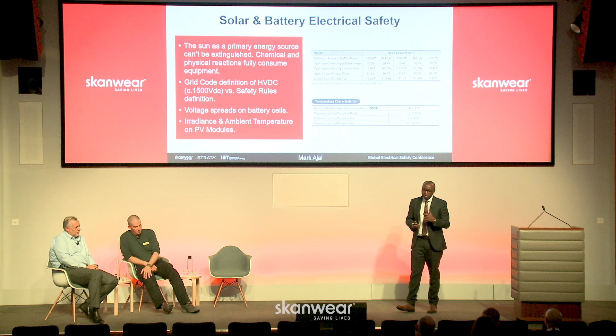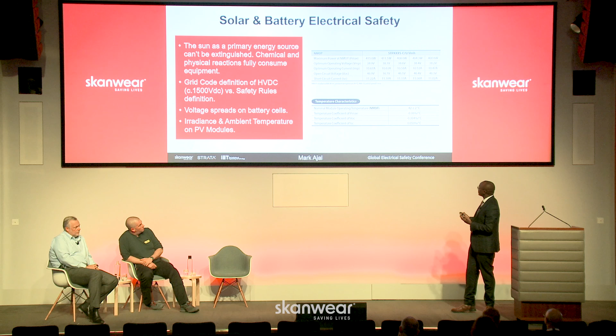The other bit is on PV modules. As irradiance changes, sometimes within seconds, suddenly you've had a sunny day and you have a massive bit of cloud cover, that change from the primary energy source means your conversion is giving you different spreads of voltage within the facility. I've included something around a data sheet of a typical PV module. And this bit, these coefficients, the temperature coefficient of our open circuit voltage, is an inversely proportional value. That creates a problem for us, which we need to deal with from a design perspective: you need to do temperature corrections for open circuit voltage. And you do those corrections for worst case combinations.